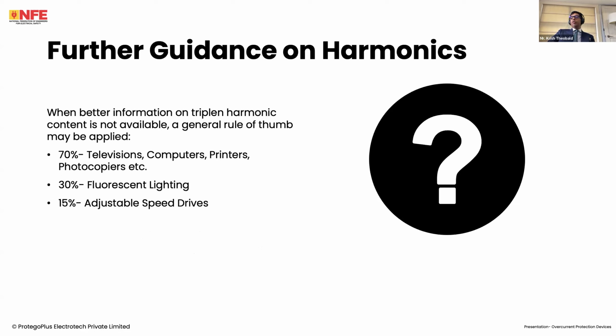Now, what value of total harmonic distortion do I consider? As a rule of thumb, 70% for electronic equipment like televisions, computers, printers, photocopiers, etc. 30% THD for fluorescent lighting, 15% for adjustable speed drives, and so on and so forth. So, very normal, 70% for IT equipment.